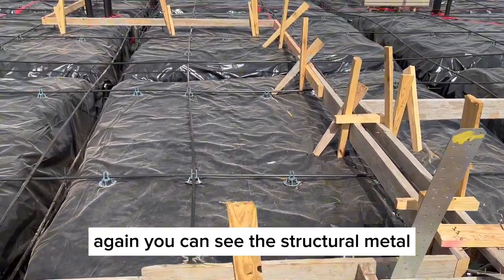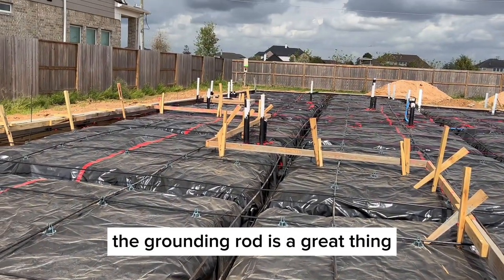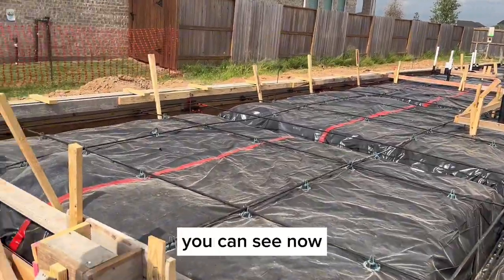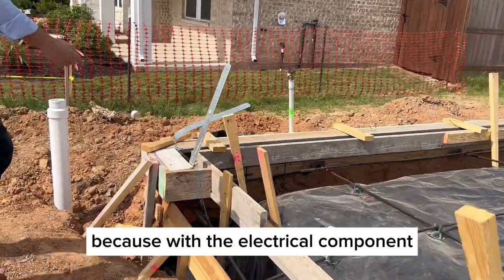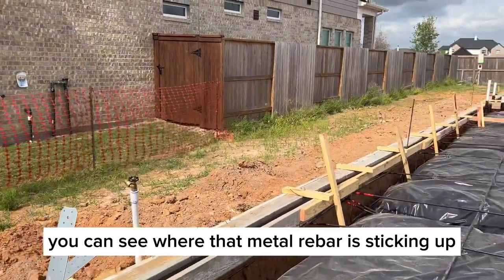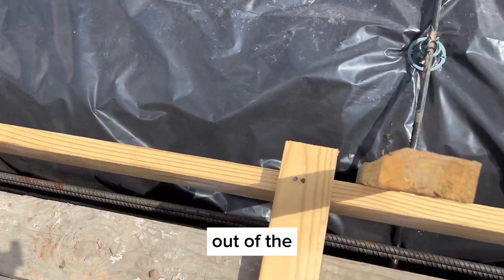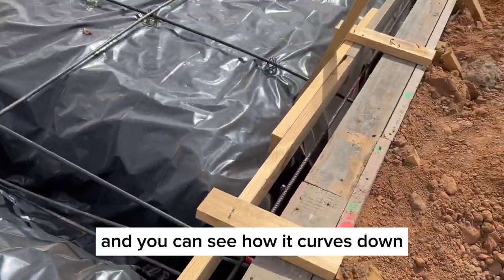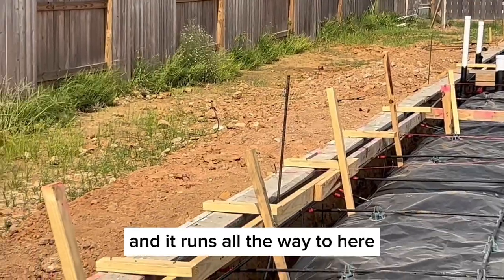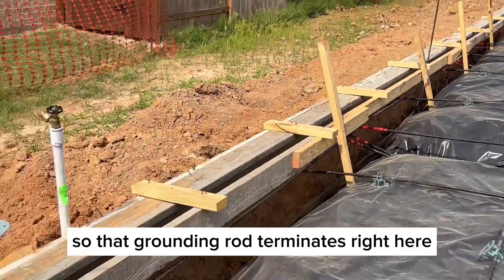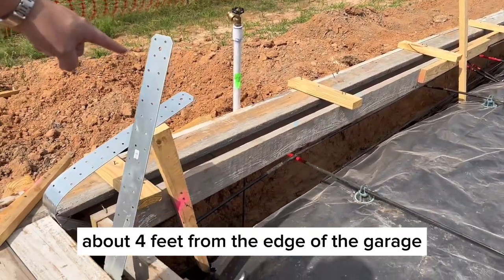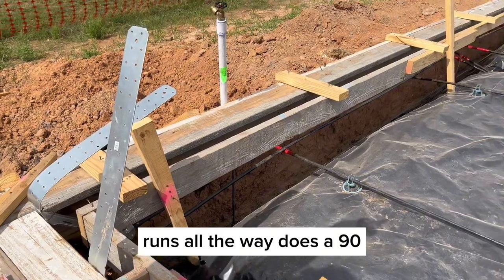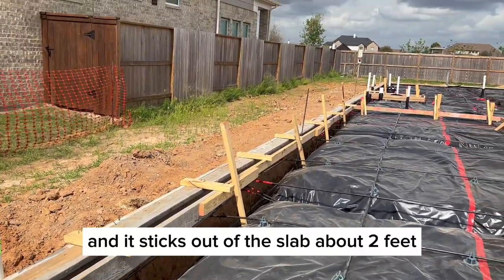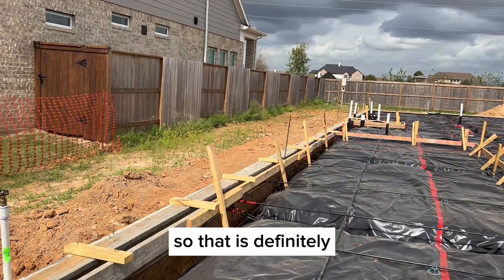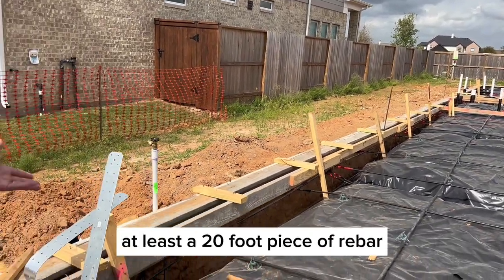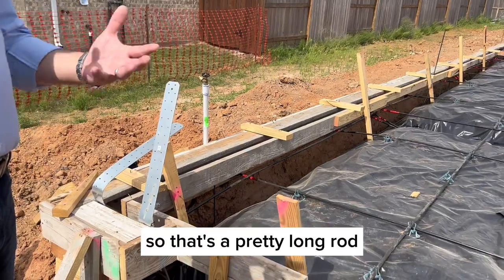Again, you can see the structural metal, and you can see the grounding rod, which is a great thing to see now with the electrical component - that metal rebar sticking up out of the edge of the slab. You can see how it curves down and runs all the way to here. So that grounding rod terminates about 4 feet from the edge of the garage, runs all the way, does a 90, and goes up, sticking out of the slab about 2 feet. So that's definitely at least a 20 foot piece of rebar, 15 to 20 feet - a pretty long rod.